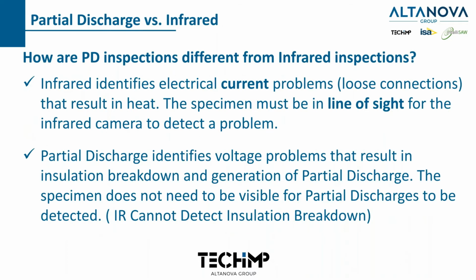I get this question a lot. What's the difference between partial discharge and infrared? Or actually, more so, I get the question: does partial discharge replace infrared testing? And the answer is no, it does not. They're two completely different tests. Infrared testing is more of a resistance test, a heat test for high resistance. And partial discharge, again, is an insulation test. All right, IR cannot detect insulation breakdown. So both tests very important, but two completely different tests. And most people will test for infrared, but they're not testing for partial discharge, and it's a very important test.